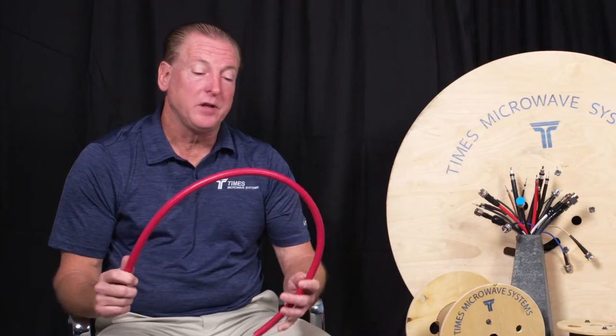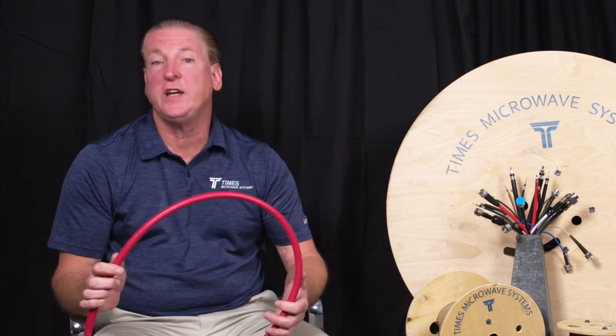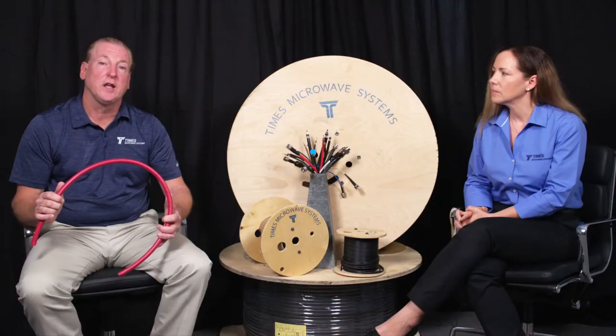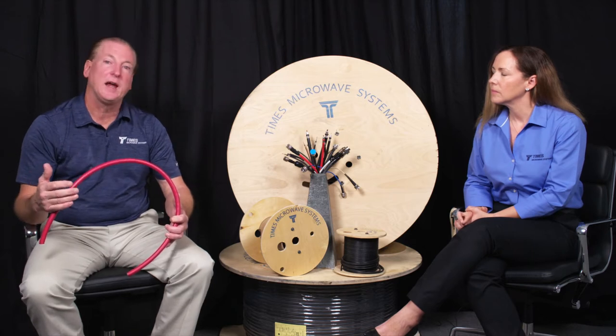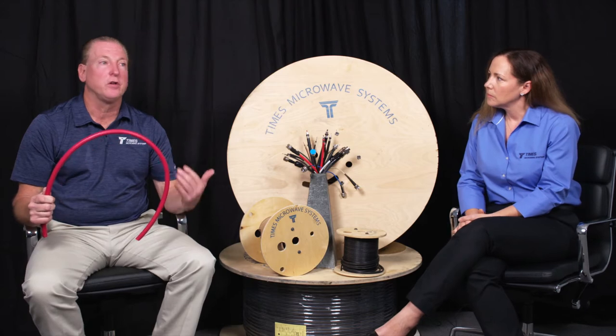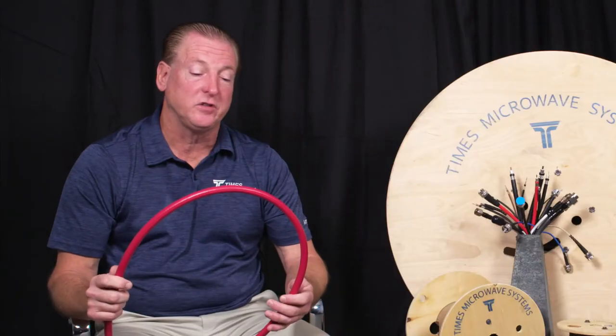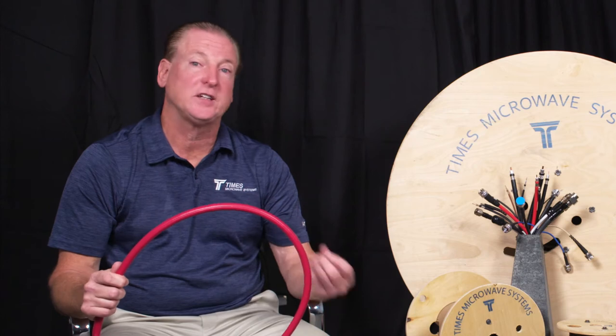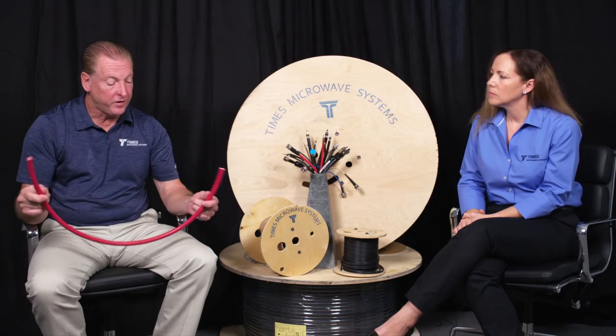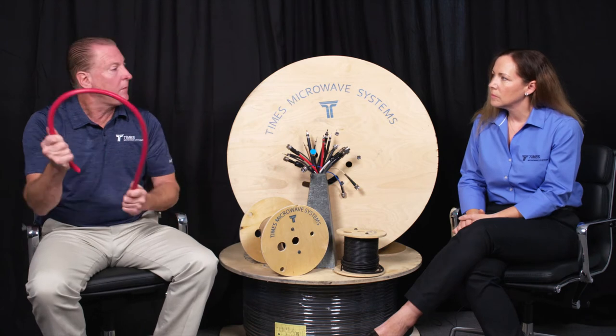This cable is qualified to type CMP listing, which CM in the National Electric Code stands for communications cable and P for plenum. Any cable that's used in an air return handling section of a building needs to meet plenum requirements per the National Electric Code and the National Fire Protection Association.